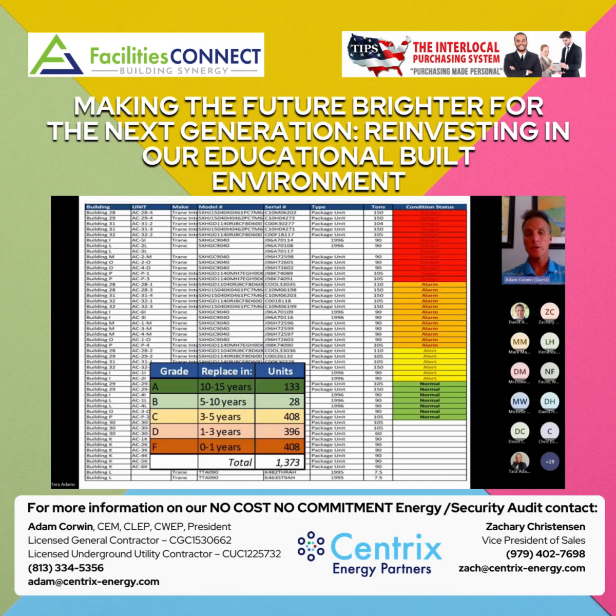This slide is actually two slides sort of superimposed. The larger one in the background shows you the make, model, and serial number, and will capture nameplate data. And then the colors on the right, the red, orange, yellow, green, think of that almost like a stoplight. Red is a danger, we need to replace these. Green is normal, keep going. And then the yellow, orange is potentially something in the middle.